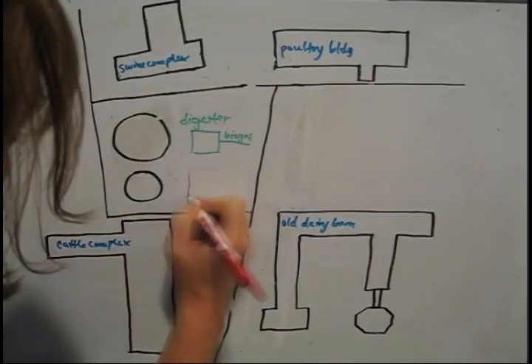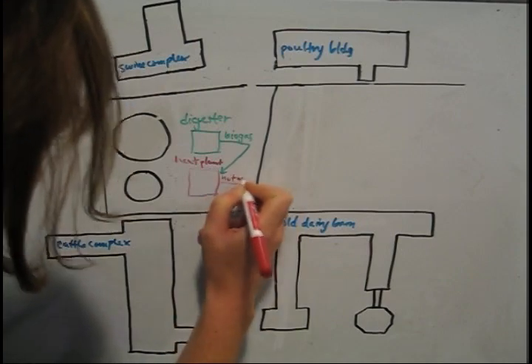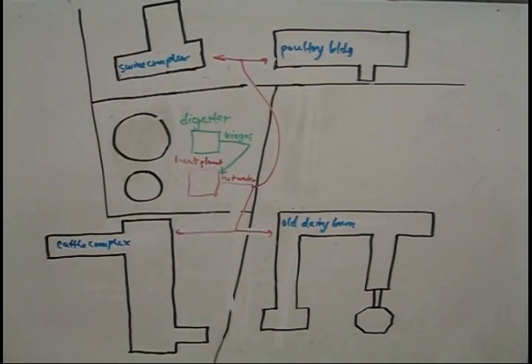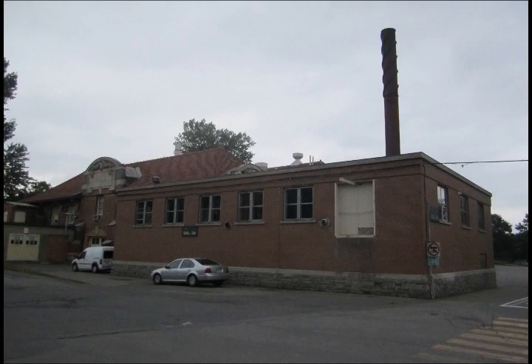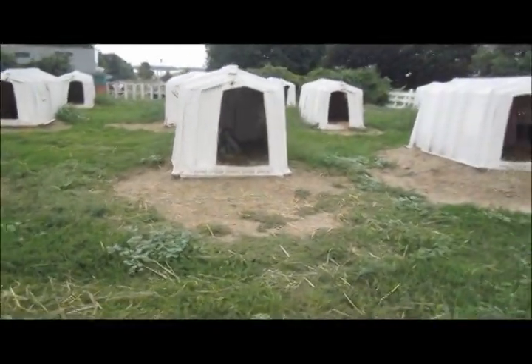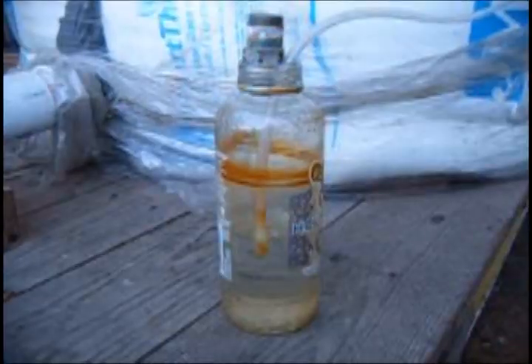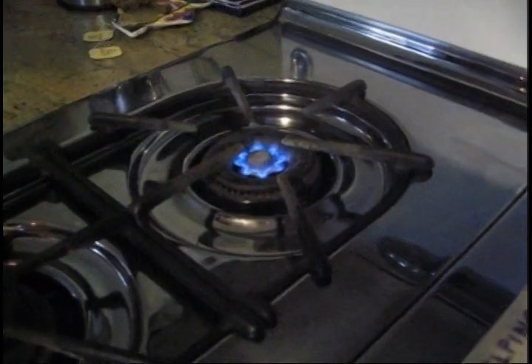A third option is creating a district hot water heating system powered by biogas for the four buildings. To use the biogas for heat, a secondary fuel source like natural gas is necessary in case the digester stops working or biogas production doesn't meet the building's heat needs. A dual fuel burner is needed to accommodate the biogas and natural gas, which have slightly different compositions.